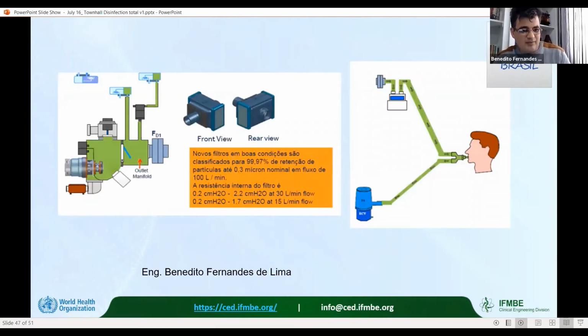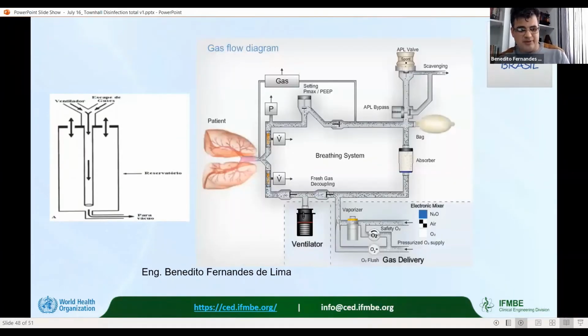Some equipment has about 20 parts to disassemble, sterilize, and then reassemble. Moreover, the flow sensors cannot bear the sterilization process. So they are immersed in alcohol to be disinfected according to the manufacturer's manual. Some anesthesia equipment is used only in patients with coronavirus. This way, we increase safety.